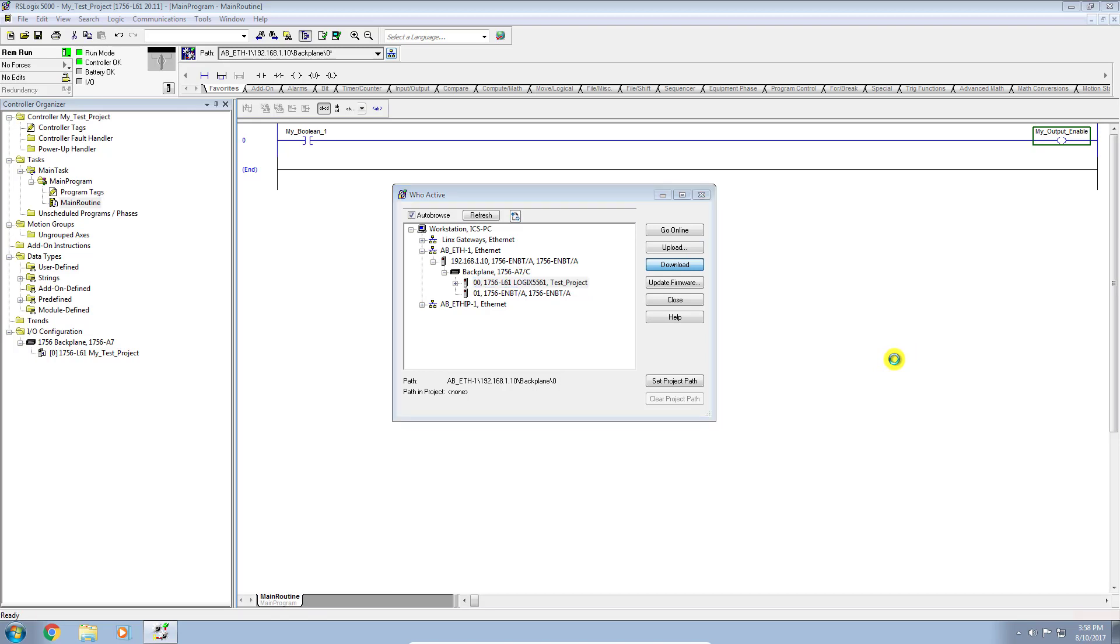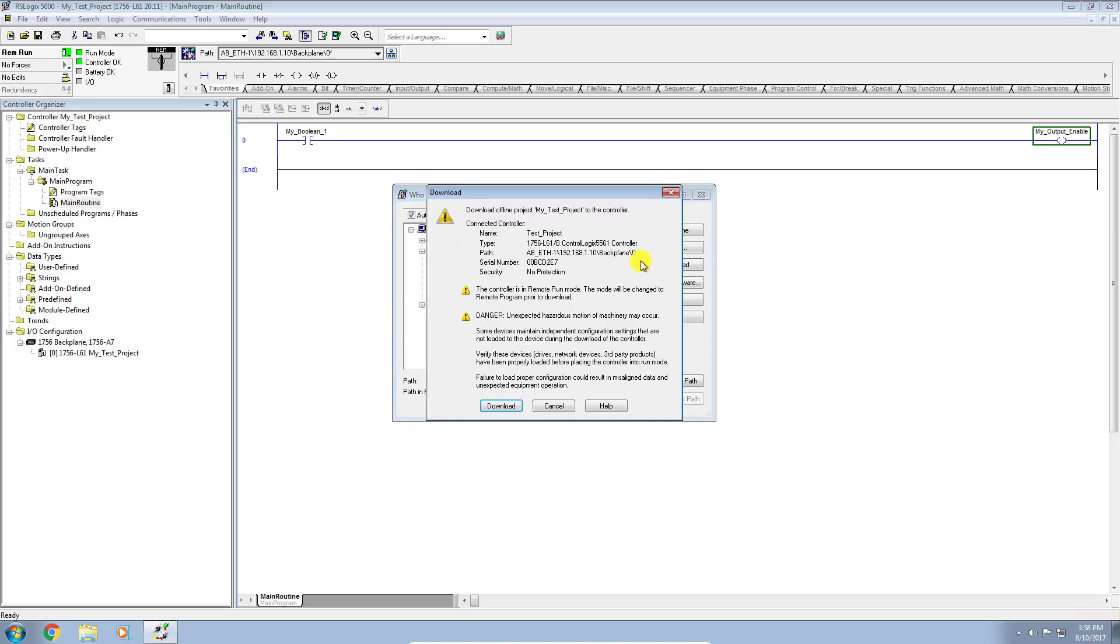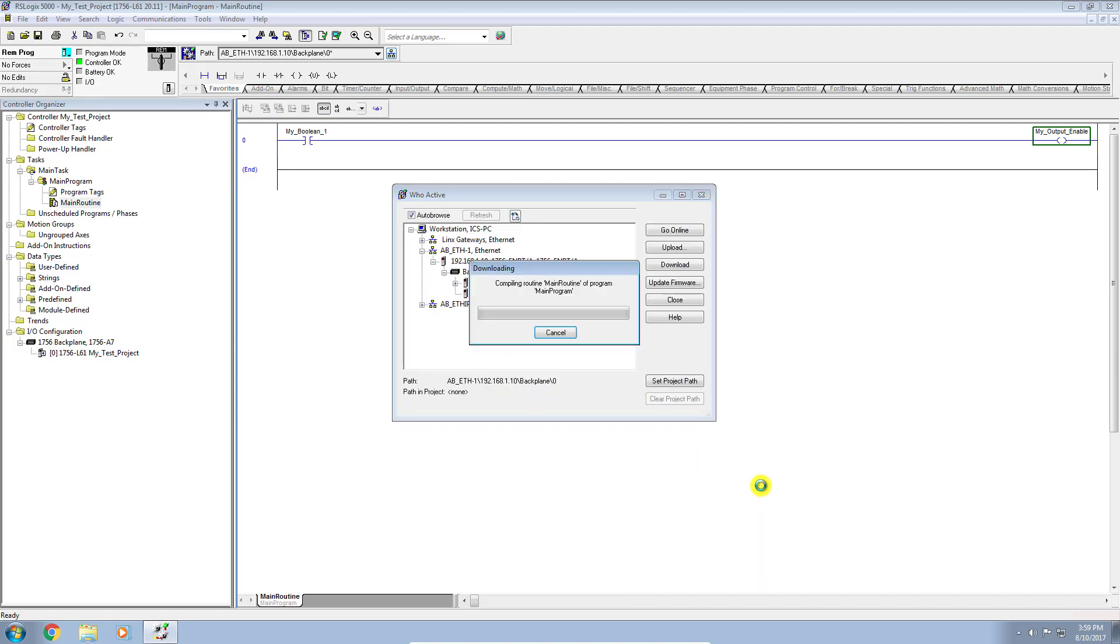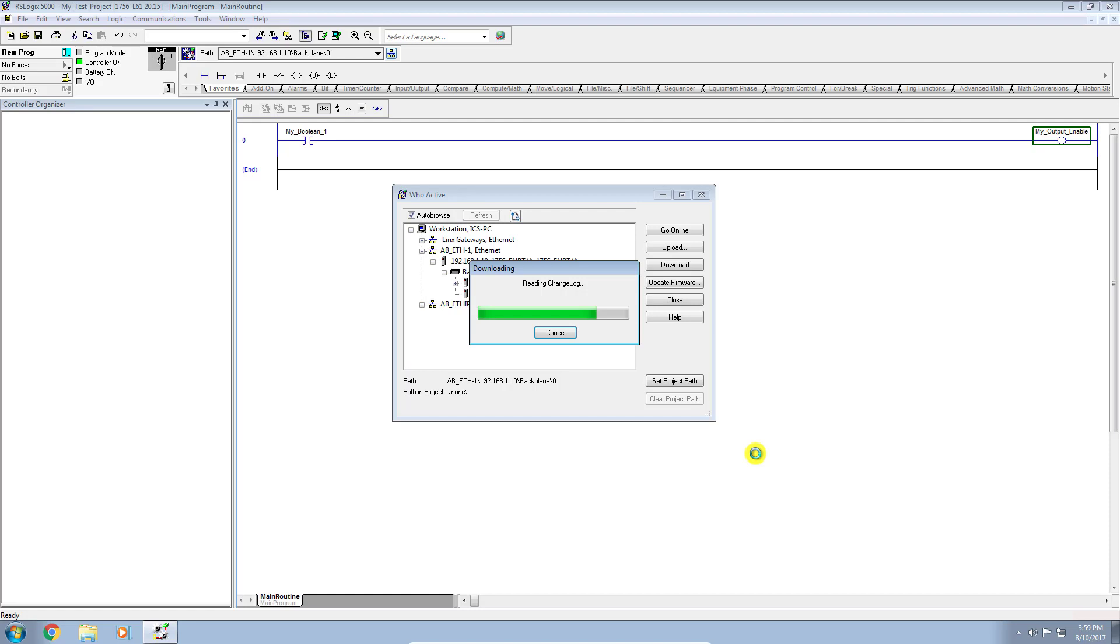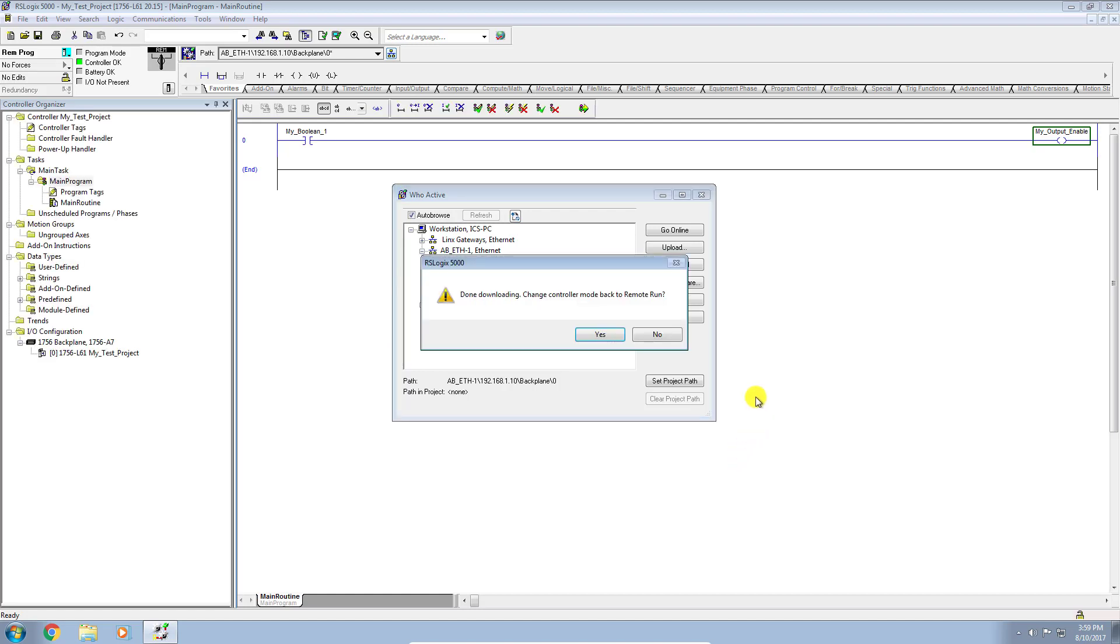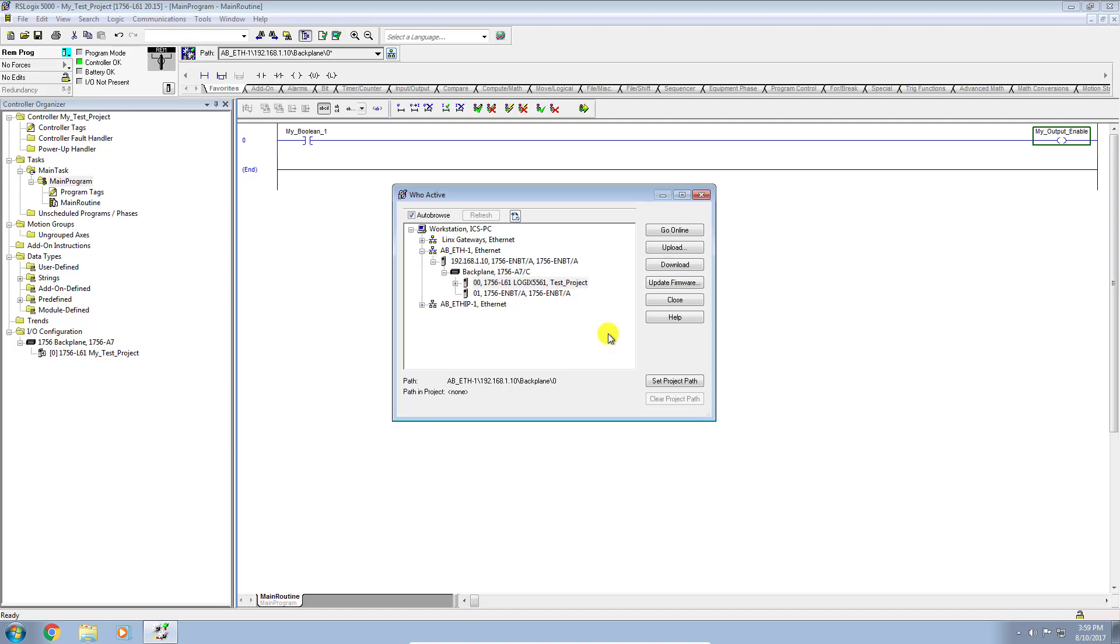And if all goes well, I'll get a warning. Here it is. If you're downloading to a running machine, make sure that the machine is in a safe state in which to do so. Okay, so we're going to say okay, go ahead and download. We're compiling our routines now. We're downloading into the controller. And it's asking me, do you want to put it back into remote run mode? I'm going to choose yes.